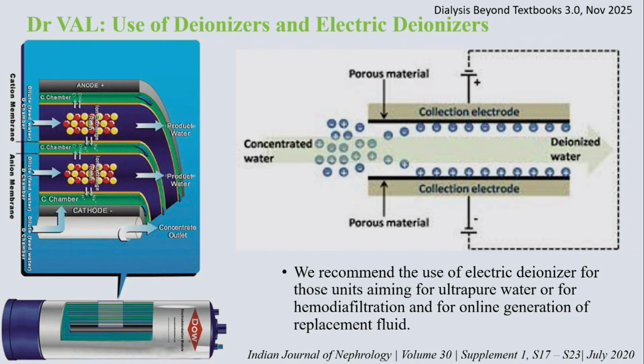It's also self-regenerating. All that happens is that the polarity of the plates is reversed and a stream of water flushes all the accumulated ions to drain. So that obviously has advantages. If you don't use it, mixed bed cation anion resins work extremely well in providing mineralogical purity. Deionizers were maligned for many years as being a source of bacteria. It has never happened, for the simple reason that if you use a strong enough acid and alkali, no bacteria grows. And if you do your regeneration regularly, now we do it twice a week at least, and that's because we have good quality water. Otherwise, we might have to do it every day.